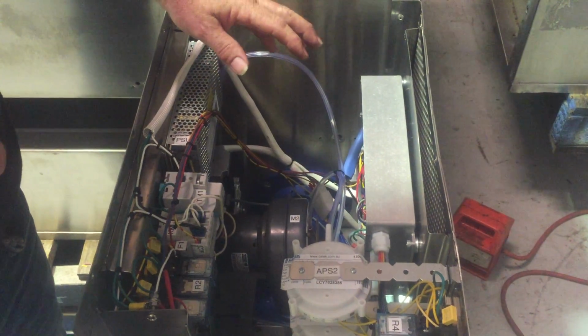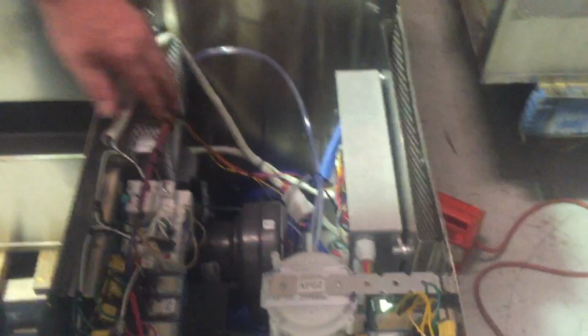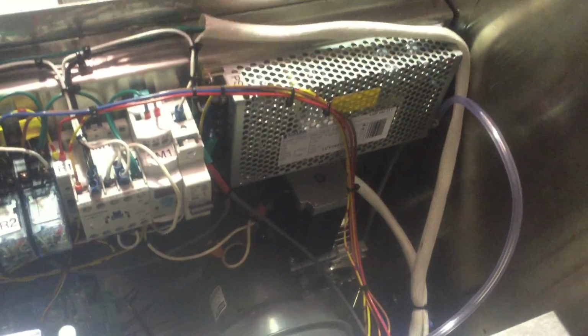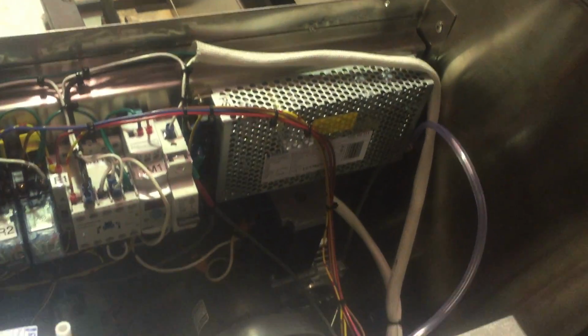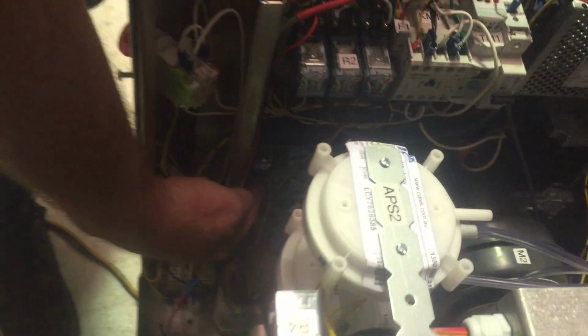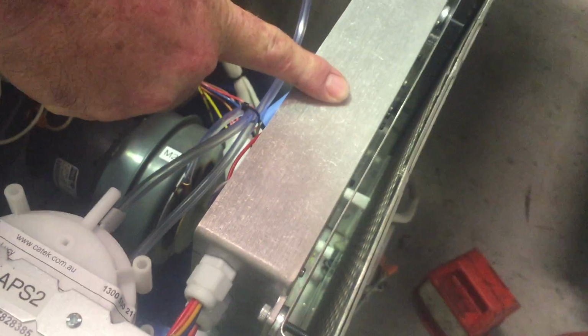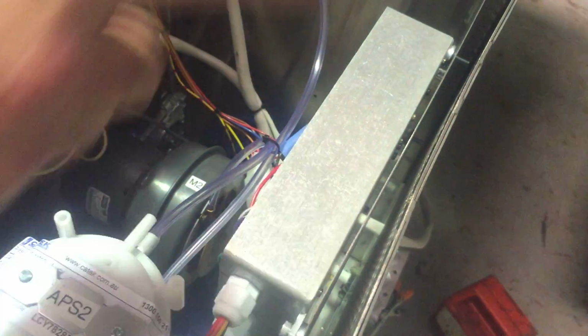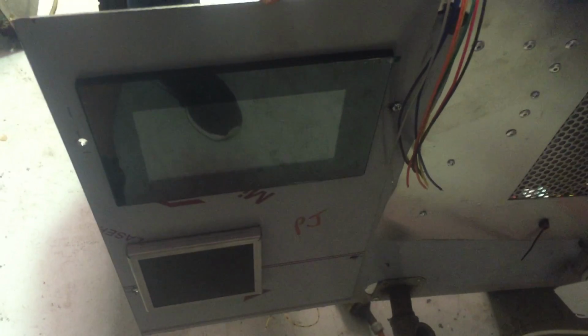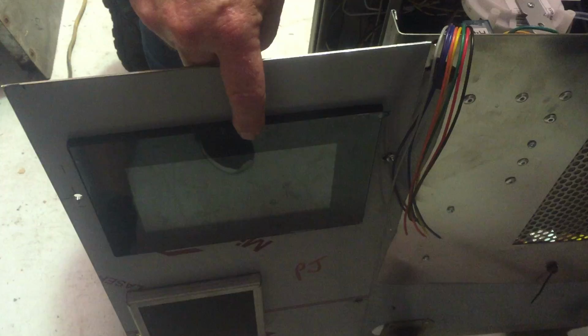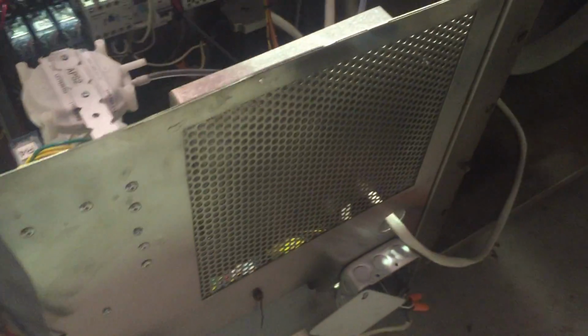The conveyor system now is run through a smaller power supply unit here. So it's got a new conveyor motor in there? Yeah, the new conveyor motor down there. It's all digital. The conveyor motor driver is just down in the corner here, which is driven by the controller, and the controller is via the touchscreen numbers. So you dial in your numbers that correspond to the speed.